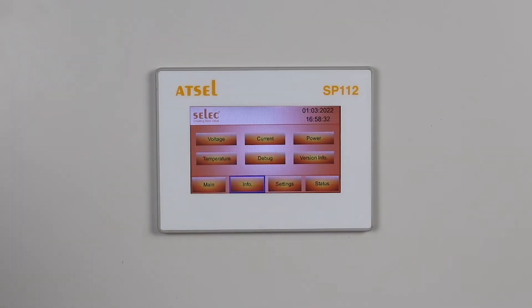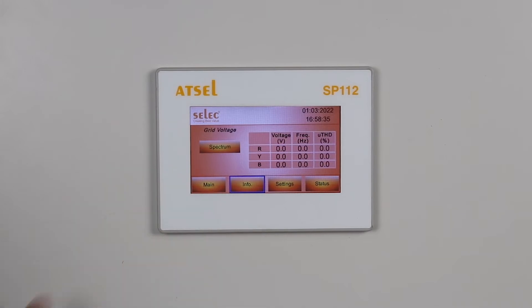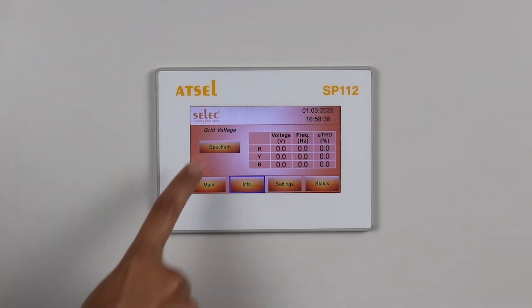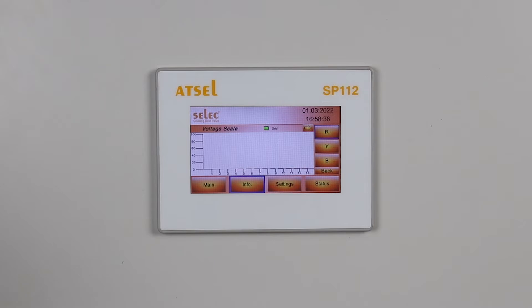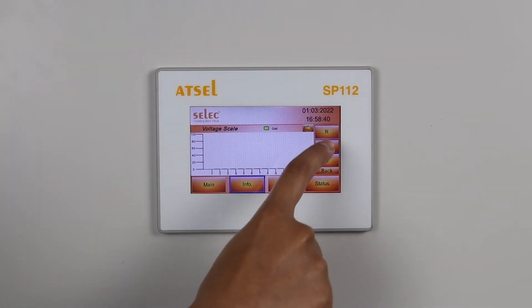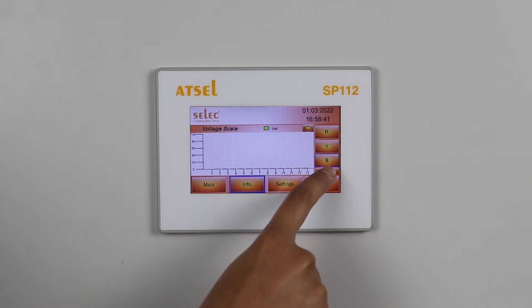In the info screen, there are various sub-menus: voltage, current, power, temperature, debug, and version info. Voltage shows all R, Y, B — all 3 phase voltages — 3 phase frequency, and THD value of voltage. Spectrum displays a harmonic bar graph up to the 50th harmonic. This is for R phase; similarly for Y phase and B phase.